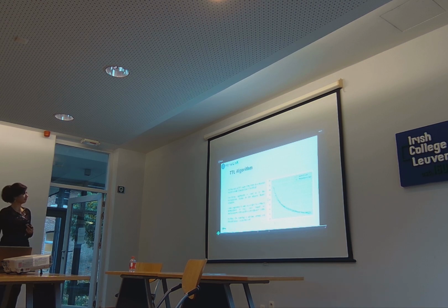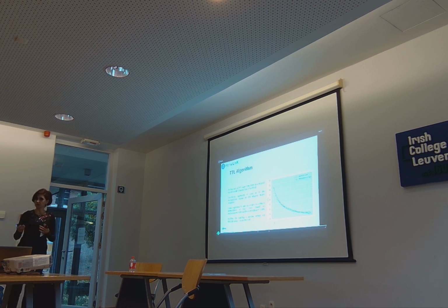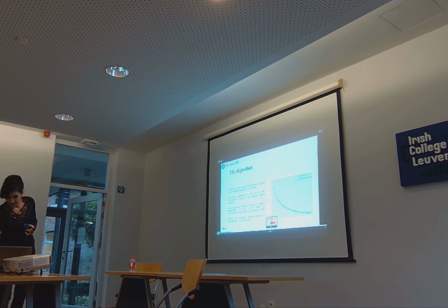What is the TTL algorithm? The TTL algorithm uses a physics-based model relying on Newton's law of cooling. It uses nonlinear regression to match the temperature changes in the model, and it uses linear regression to figure out the average temperature of each room, considering the temperature outside and the temperature of nearby rooms. Sudden temperature changes, like when windows are opened, are detected and removed through Z-score methods to keep the data more valid.